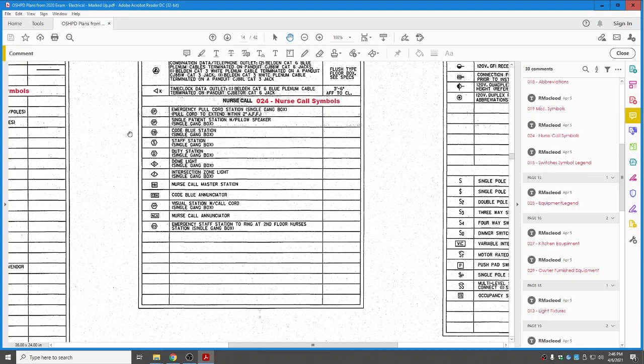NM is a nurse call master station that would be located at the typical nurse call station. We have a code blue annunciator, which would also typically be located at a PBX or at the nurse station. VP, visual station with call cord. Nurse call annunciator, which would typically be at your nurse call or nurse station desk in a patient area. And ES, an emergency staff station to ring at, in this case, the second floor nurses station. So there's some of our symbols. We're probably only going to see 4 to 6 of these typically on the majority of the rooms. Let's jump to one of those rooms now.